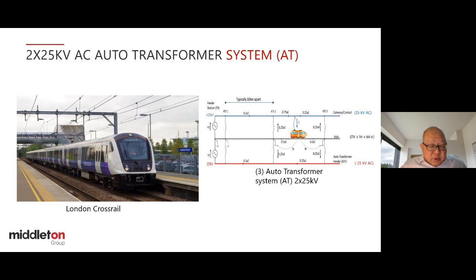Now, what are the pros for this system? 50 Hz leakage current is confined and controlled. The action of the AT pulls the rail current and the 50 Hz leakage current out of the earth to return to the center tap of the auto transformers. The opposing currents flowing in each subsection produce opposing, cancelling magnetic fields, resulting in EMC performance that is superior to both the rail return and the booster transformer systems.